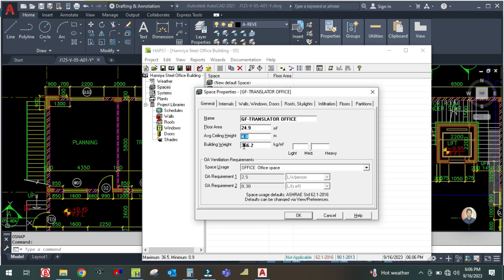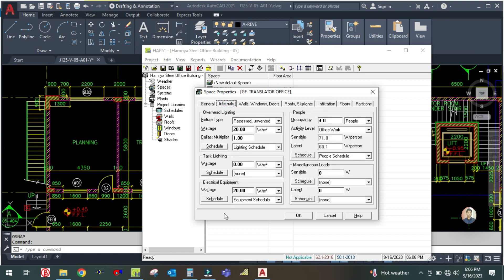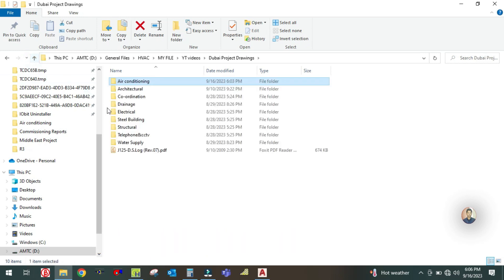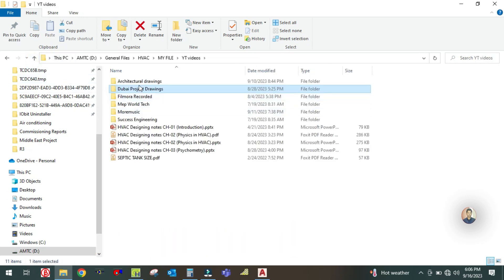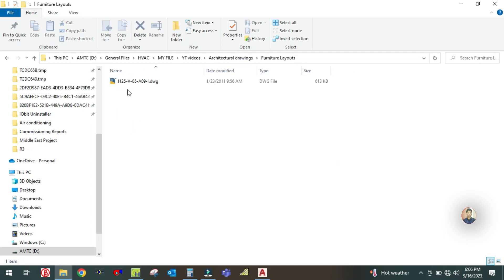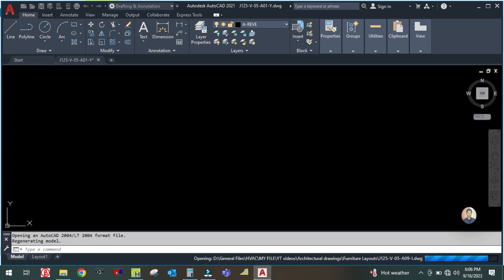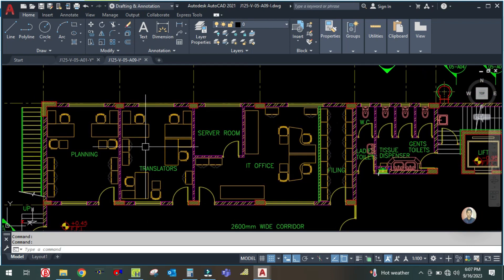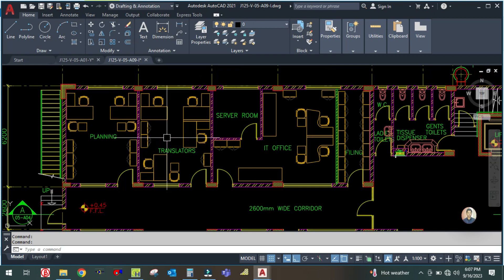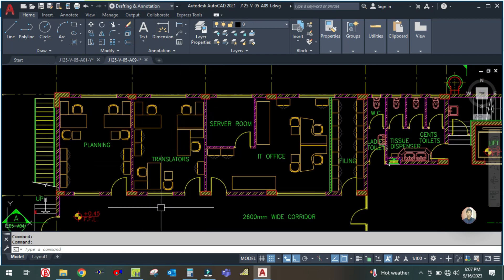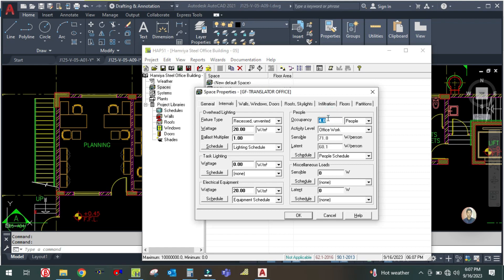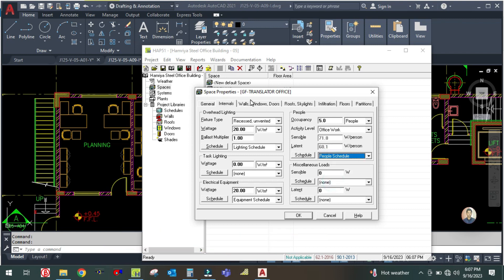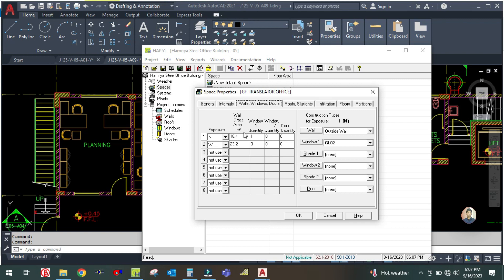Go to the internals. In the internals you just need to change the number of people, which will be taken from the furniture layout. Let me open the furniture layout — you can see there are five chairs, so the total number of people will be five. Interior number of people: five. They are doing office work, so select the schedule here as 'people', then go to the exposure which covers walls, windows, and doors.